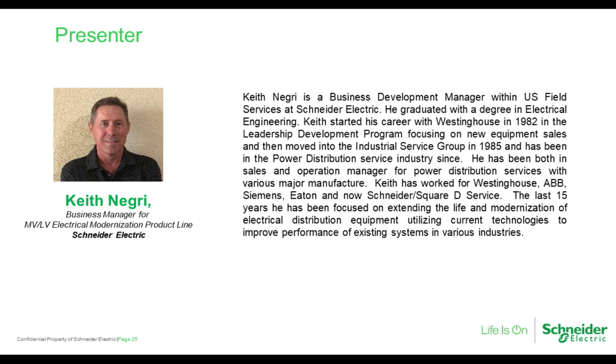Can you talk about refurbishing used circuit breakers? That is the new buzzword for 2020, because the new code came out for 2020, the NEC code, regarding reconditioning of equipment. And there's still a lot of conversation, to be honest with you, about interpretation of that new code and analyzing it. The real reason for that new code for reconditioning breakers was because of safety issues. And we want to make sure that in that reconditioning process it's done to the best of ability and also to the standards today.